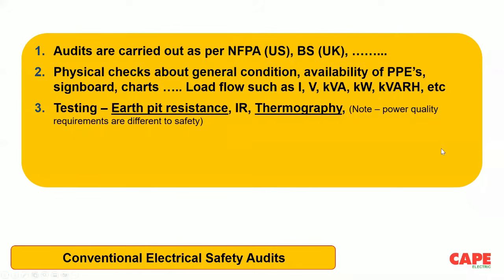Also, I've underlined 2 things, the earth pit resistance measurement and thermography. Please note that the earth pit resistance measurement was removed from the low voltage electrical safety standards a few decades back internationally, and even in IS 732, if you look at the 10 testings, the earth pit resistance measurement is not mandatory. The technology has already changed, not now, 20 years back. Similarly, thermography is not a recognized test or recognized verification mechanism in the standard which I have shown you earlier. Thermography, of course, for solar PV, yes, you can do that. But for an electrical installation inside a building, thermography is not recognized until now.